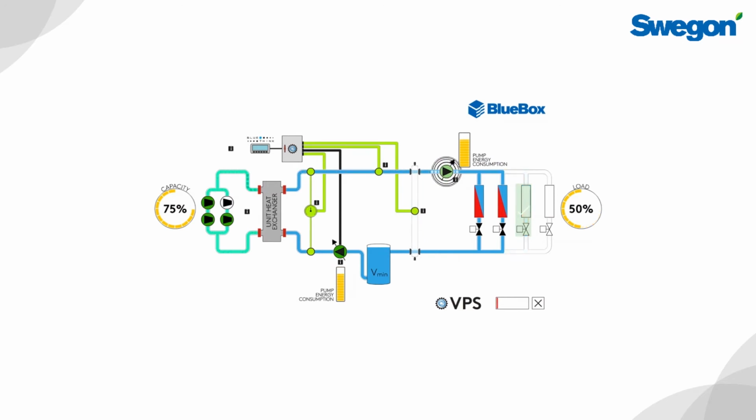pumps. As this sequence continues, the compressors offload further, the pumps reduce the flow, until such time there are no terminal units requiring any cooling. The compressors are switched off and the bypass valve opens on the primary side to provide a minimum flow through the chiller. This arrangement is the same for heating. The BMS controls the flow of the secondary pumps.